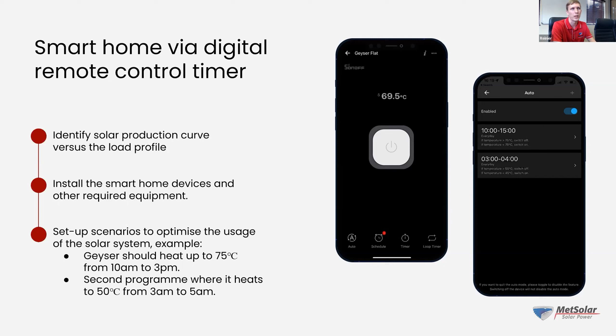Obviously, the ideal is just to have it run during the day, during sun hours. And by heating that geyser just past the 65 degree limit you'd usually have - that's also one of the reasons I'm using a smart switch rather than a Geyserwise, because I'm not capped at 65 degrees. I want to store that extra 10 degrees Celsius, which is enough hot water on a 150 litre geyser for 2 people to shower at night and in the morning.